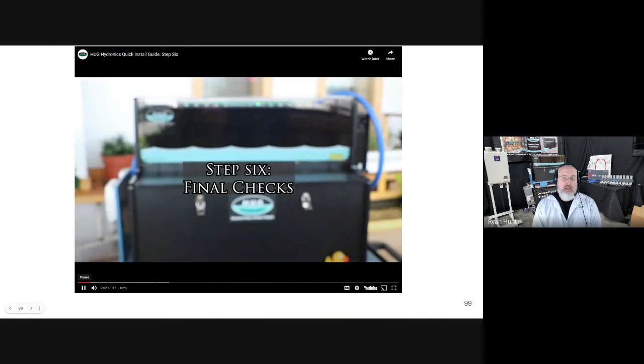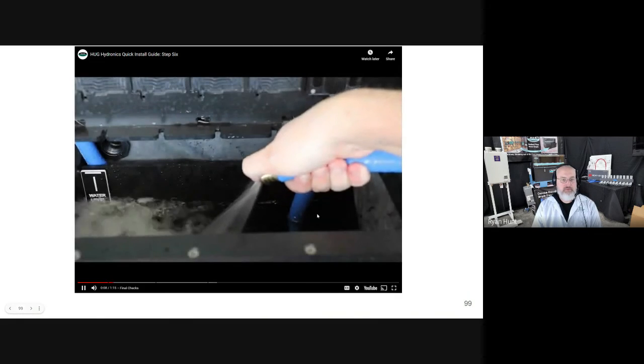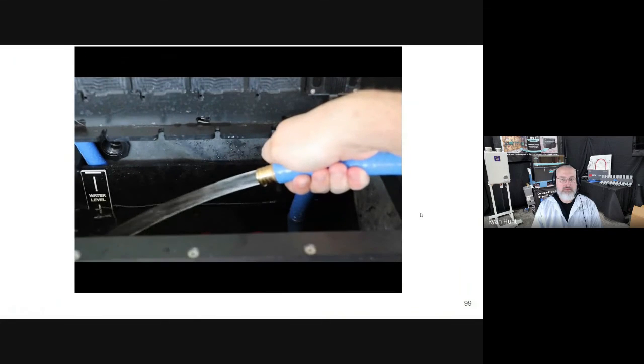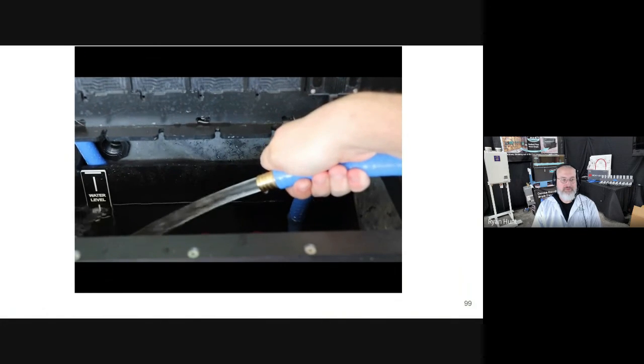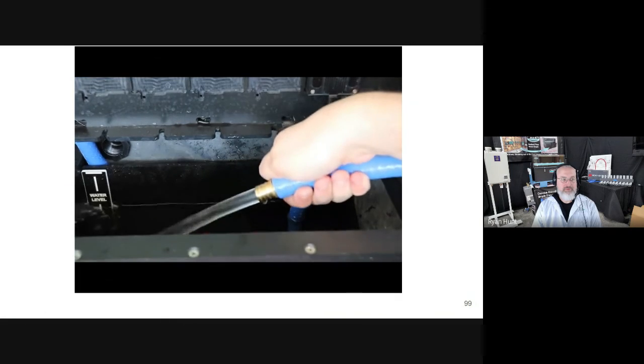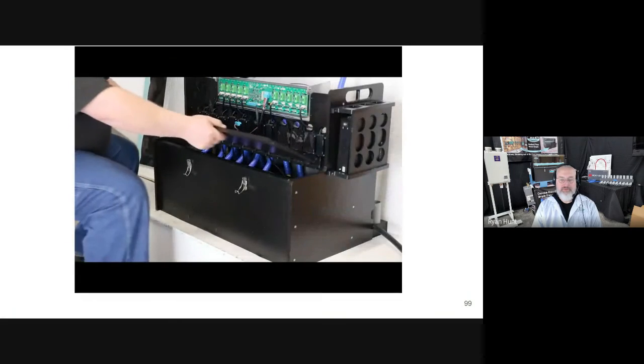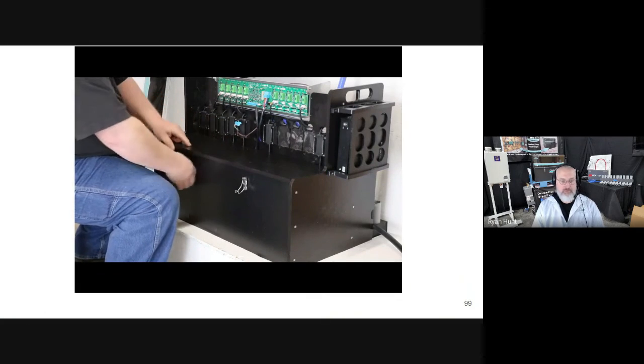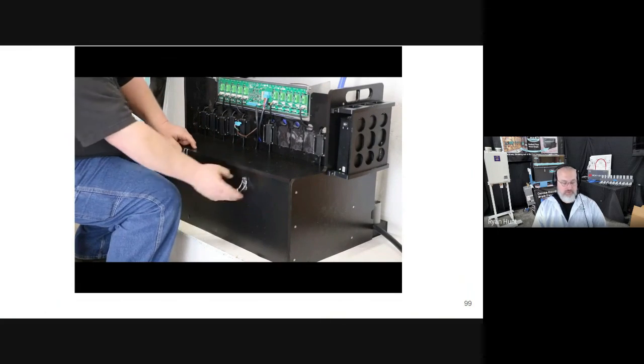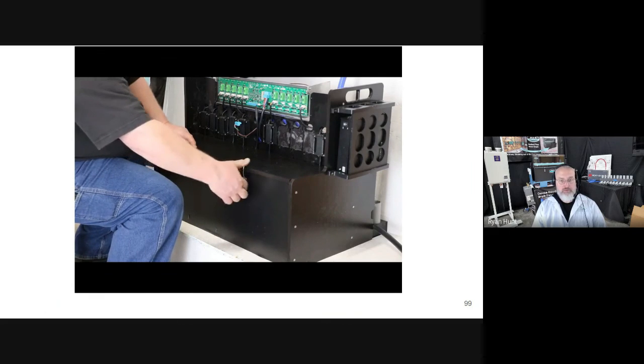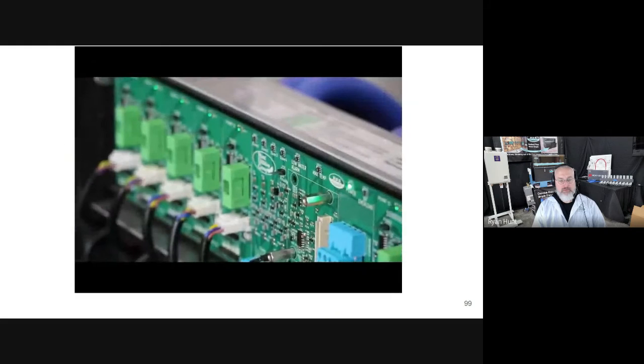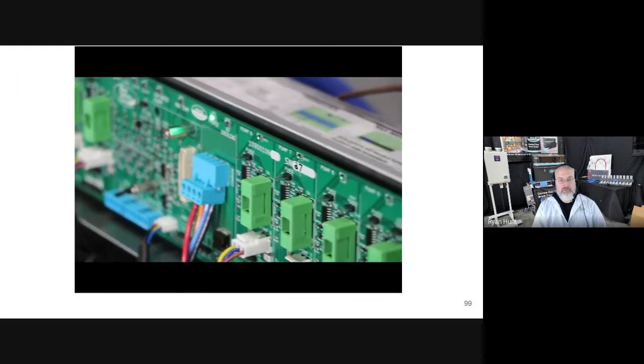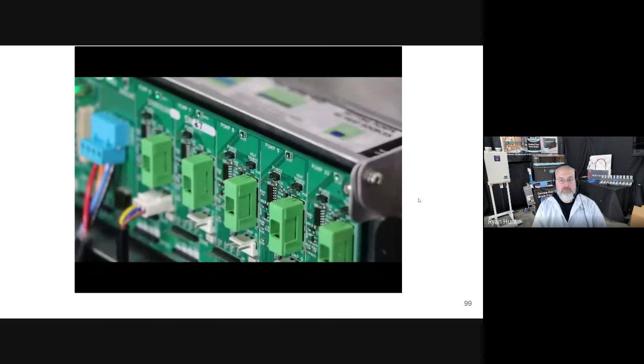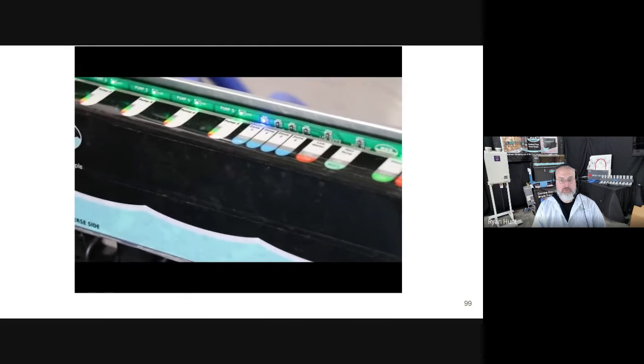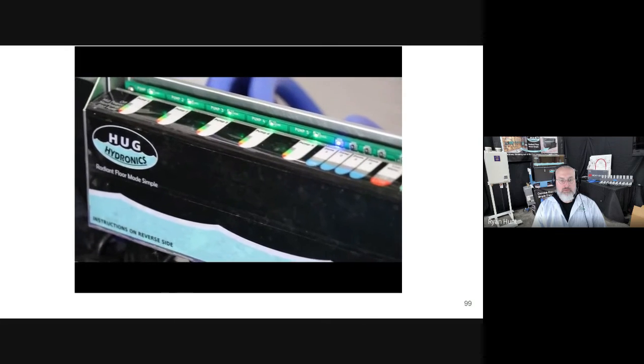Step 6. Final checks. Check the water level. Add additional water or glycol mix until you reach the upper mark of the water level indicator. As a note, we recommend adding a calendar reminder to check the water level every 6 months. Reinstall and latch the tank cover. Caution, the water may be hot. And finally, complete a final check with the thermostats calling for heat. Check that the pump indicator lights are green or yellow.